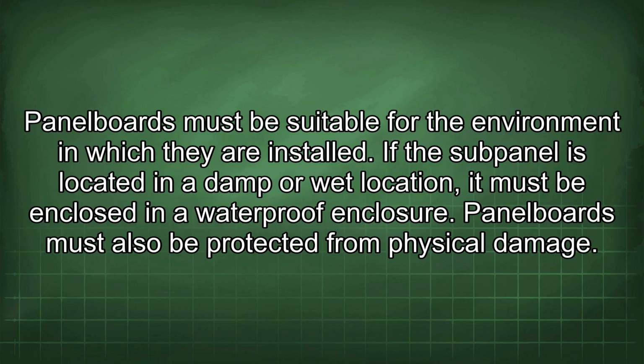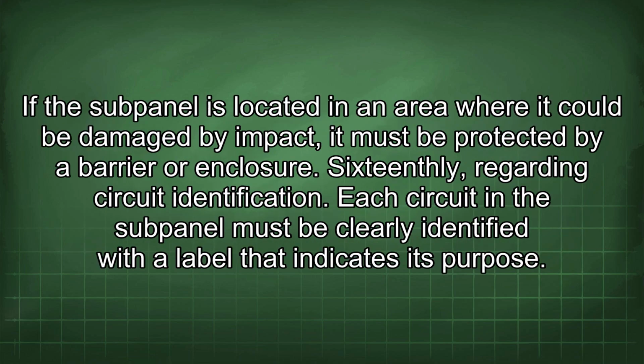Panel boards must be suitable for the environment in which they are installed. If the subpanel is located in a damp or wet location, it must be enclosed in a waterproof enclosure. Panel boards must also be protected from physical damage. If the subpanel is located in an area where it could be damaged by impact, it must be protected by a barrier or enclosure. 16thly, regarding circuit identification.